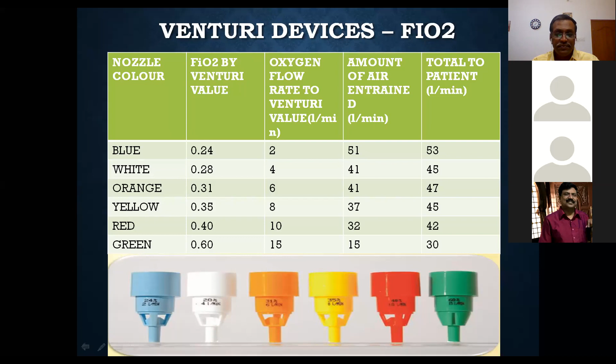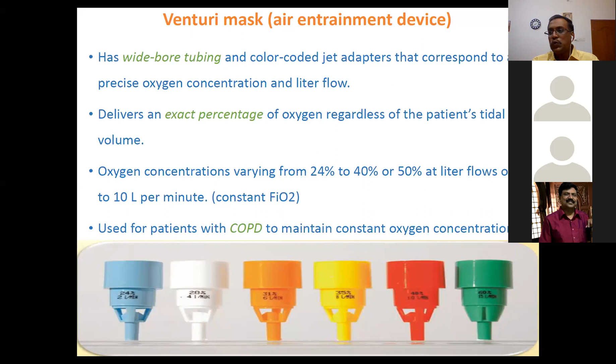So here is the wide-bore tubing. Color-coded jet adapters are present here, and it delivers a fixed percentage of oxygen regardless of the tidal volume of the patient. This oxygen concentration varies from 24 to 60 percent, with a maximum of 10 liters per minute. You can use this device for a COPD patient where 100% oxygen is not needed, as that is detrimental to the COPD patient. And we can maintain the FiO2 at a constant flow.